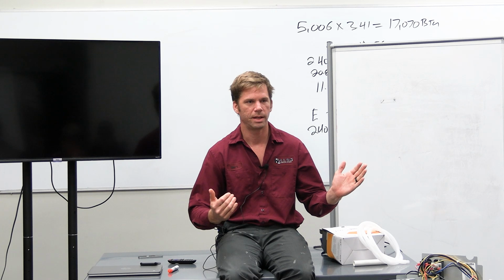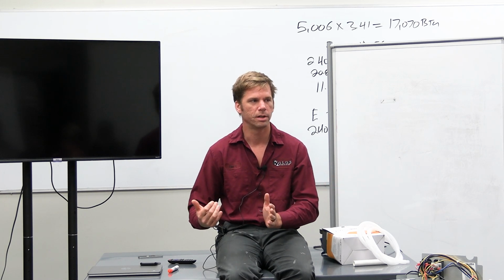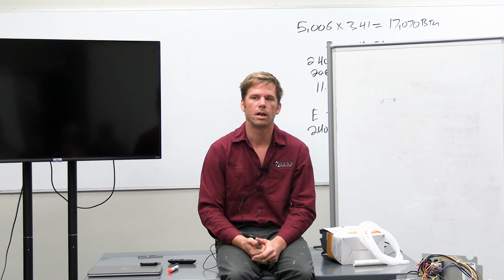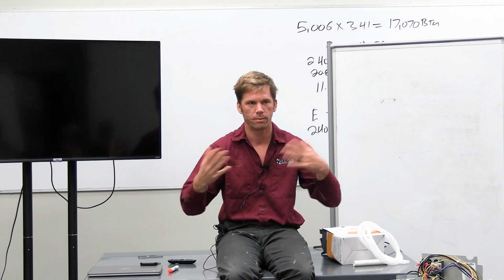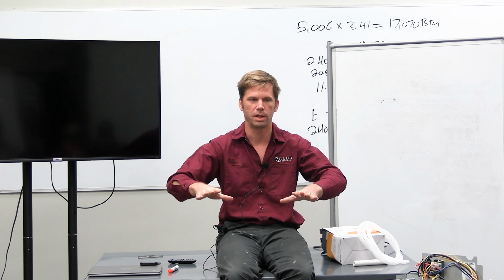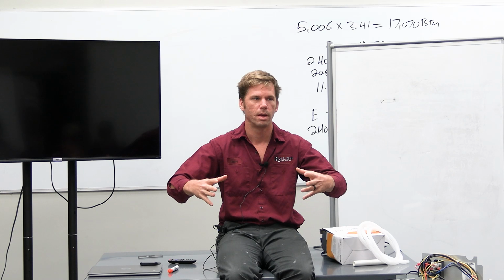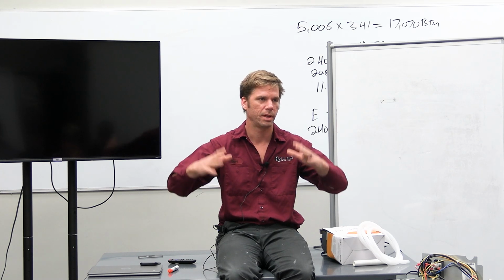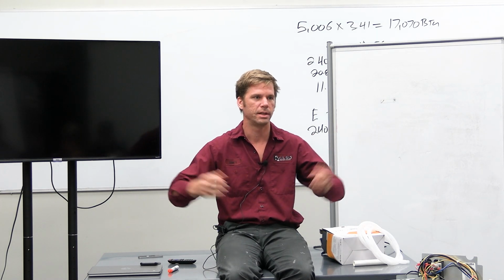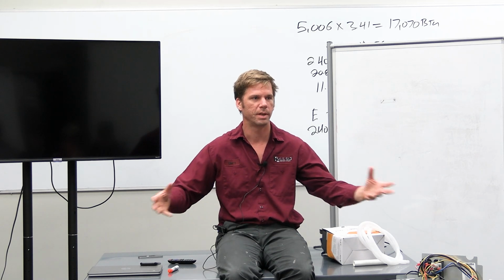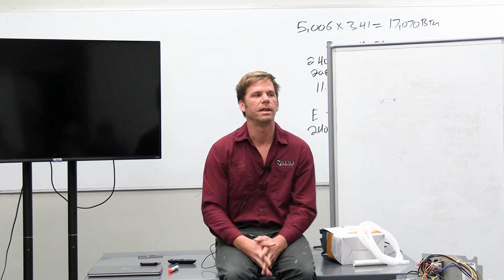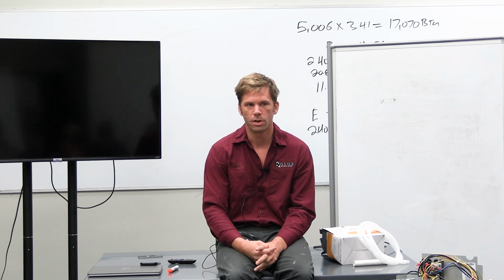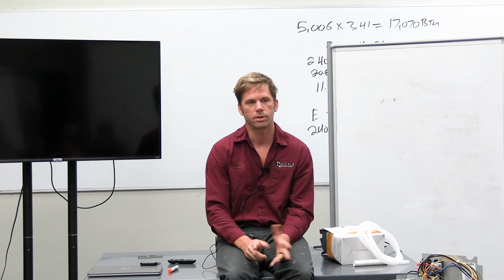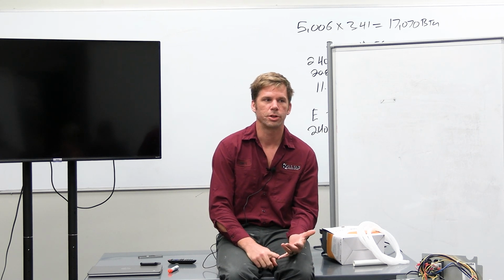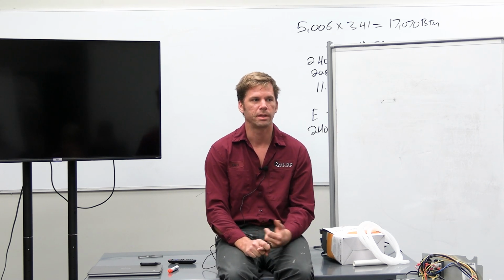If you've got a heater that is coming on and it's not burning clean, or you're getting a lot of random rollout issues, so the flame will actually light, but it won't be a clean startup and the flame will roll out of the heater because there's been so much gas buildup in there, and you have safeties that will sometimes go off on that and keep your heater from starting, you need to take extra care to check your inlet gas pressure and your outlet gas pressure the next time that thing's running.